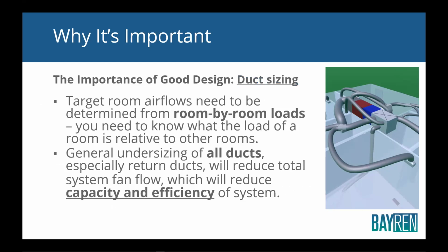I mentioned that, okay. General undersizing of all the ducts, especially the return ducts, reduces total system fan flow. And if you actually look in the air conditioner specs, the expanded data tables, the capacity tables for air conditioners, as airflow goes down, capacity goes down. So by reducing airflow, you're actually making that air conditioner smaller. The other thing is it reduces efficiency. So let's say you paid for a 3-ton, 16 SEER air conditioner, but if you severely undersize your ducts, what you're actually getting is maybe a 15 and a half SEER, 2¾-ton air conditioner. You're not getting the size air conditioner you need or the efficiency because you've undersized the ducts. So that's another important thing.